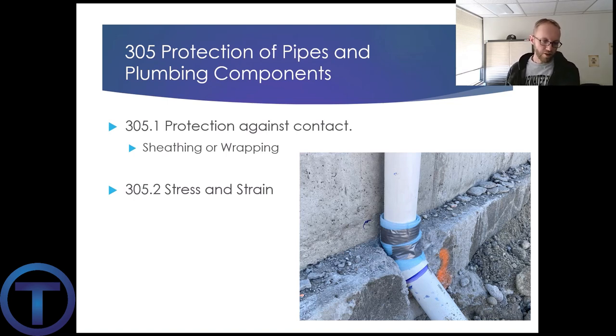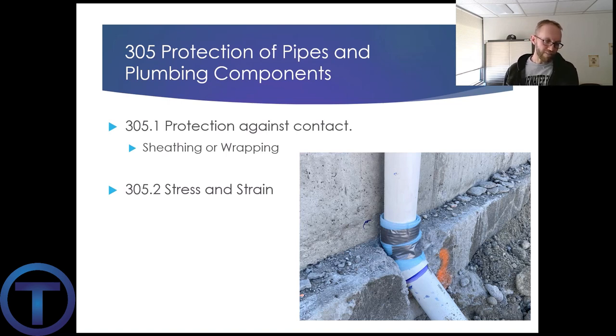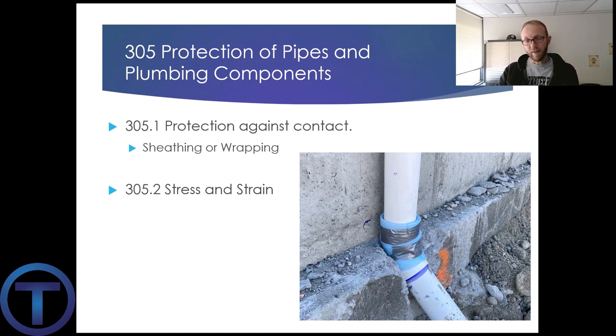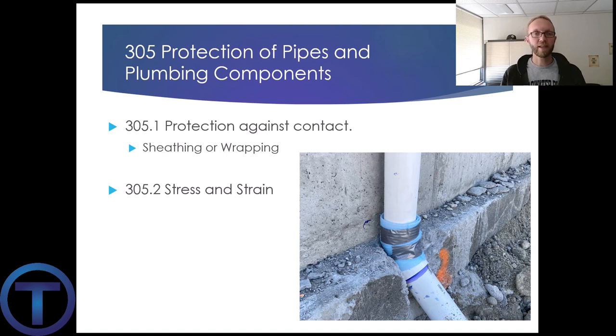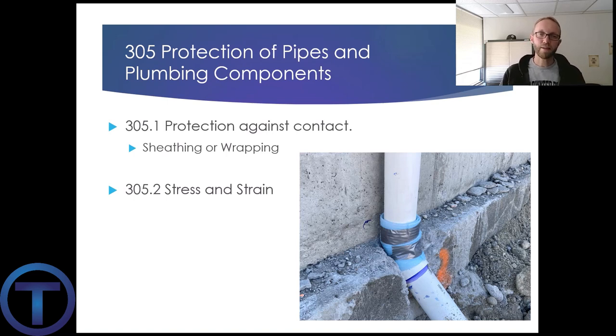Metal pipes shall not be placed in direct contact with corrosive soil — again, trying to protect those pipes. Where sheathing is used to prevent direct contact, that's like having a pipe around a pipe or wrapping it to give it some extra space so the pipe can expand and contract. In fact, if a pipe is held in place by concrete and can't expand and contract, it'll actually tear. I've made a lot of those repairs as a service plumber.